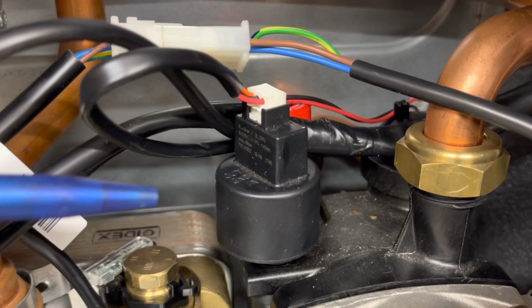Basically, how it works, it uses a flexible diaphragm inside which deforms when it's pressurized, and a transduction element transforms the deformation into an electrical signal. In our case, we have a 5-volt DC supply to the transducer, and when the pressure within the heating system measures 1 bar of pressure, it'll send a 1-volt DC signal to the circuit board. So if you have 2 bar of pressure in the boiler, you'll get 2 volts DC. So the boiler knows how much pressure is within the heated circuit.